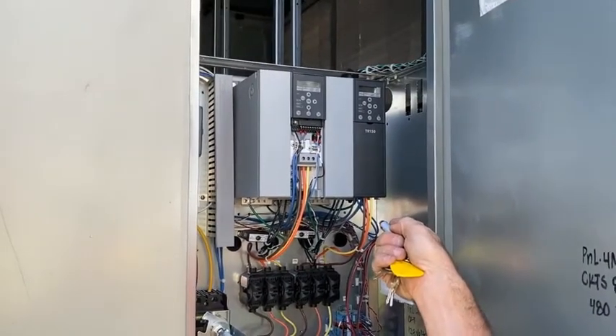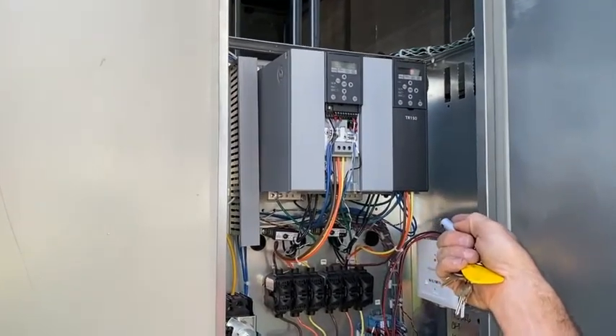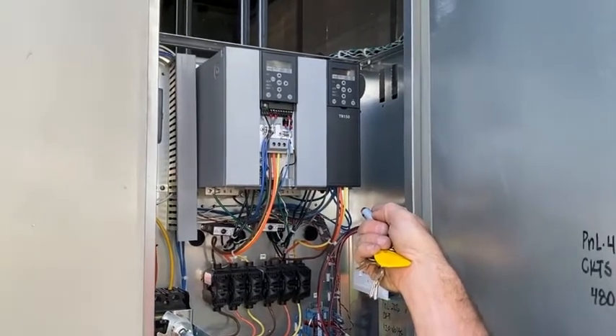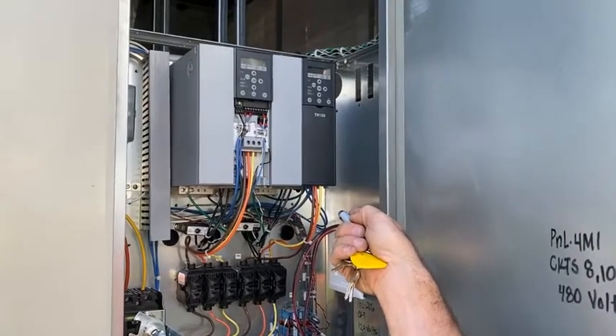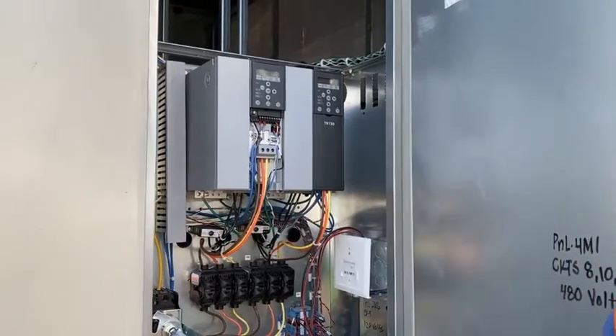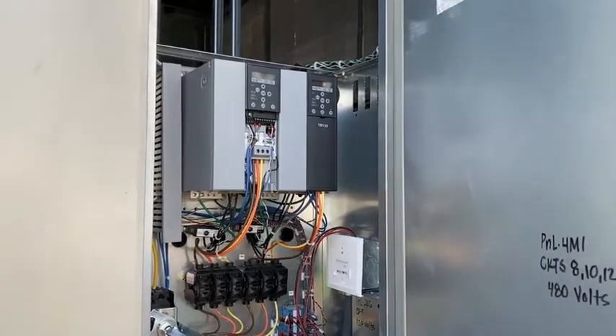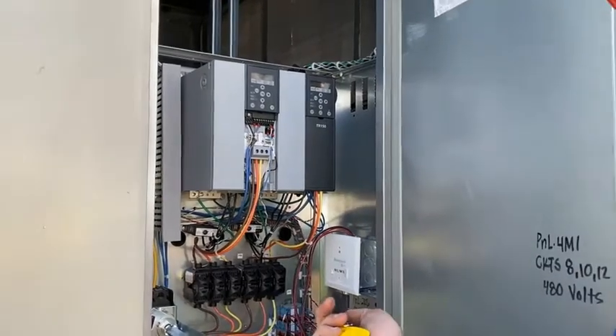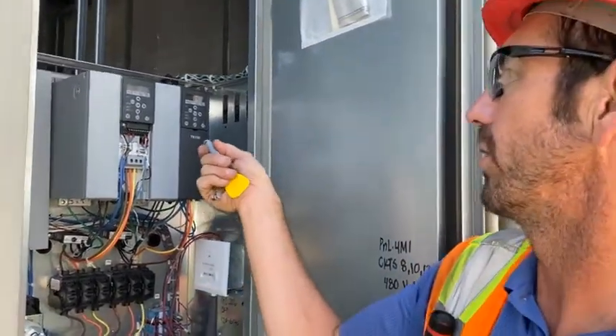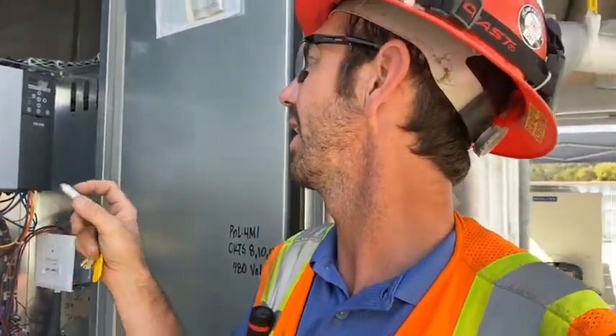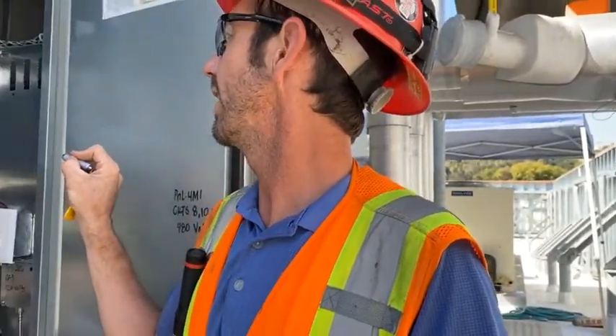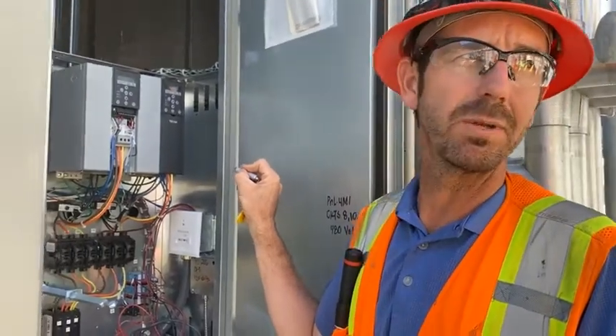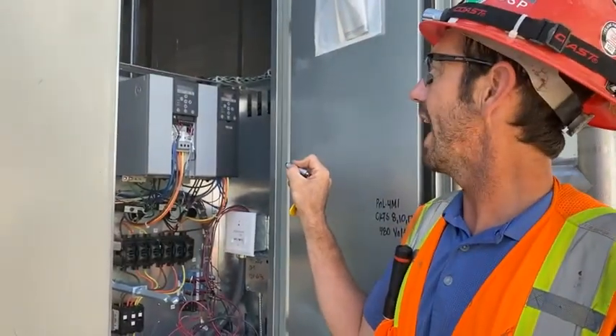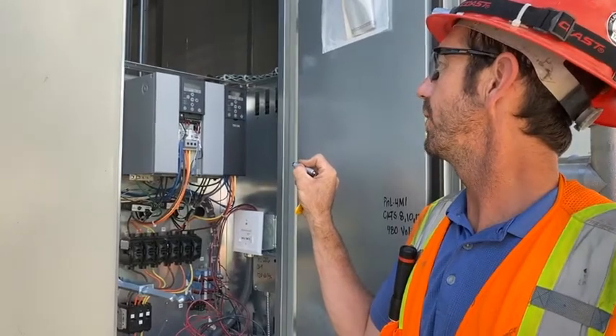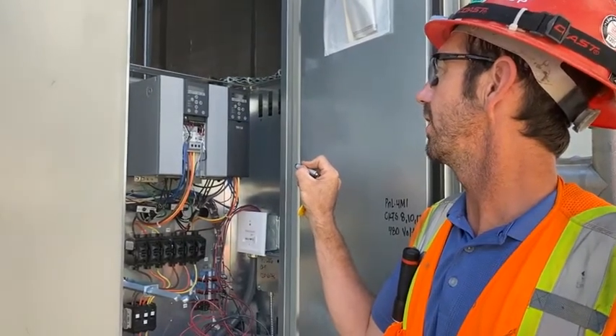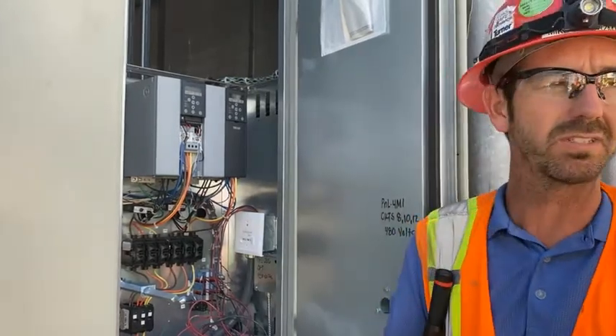So when it sees 24 volts on this input, it will turn on the drive to minimum speed. If we lose voltage to 27, because we're on coast inverse, then it will ramp the fan down. That's your safety interlocks, so your fire shutdown. If we don't get voltage back into that, it will shut the unit back off. Voltage comes out of 12 right here. It's 24 volts DC. Can you guys hear me? We're looking for that voltage here to start the unit. If we lose it on 27, it will come to a coast and stop.